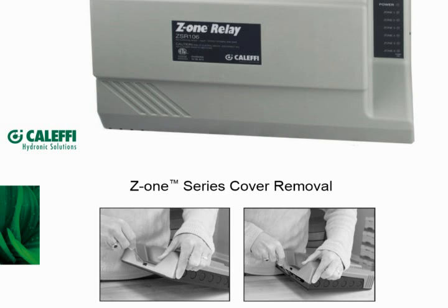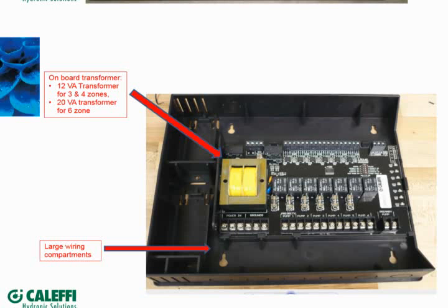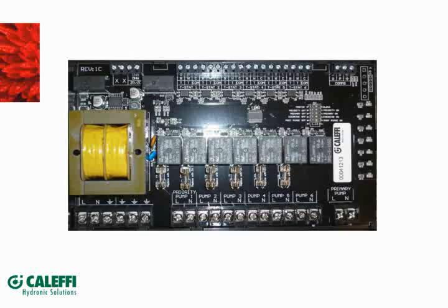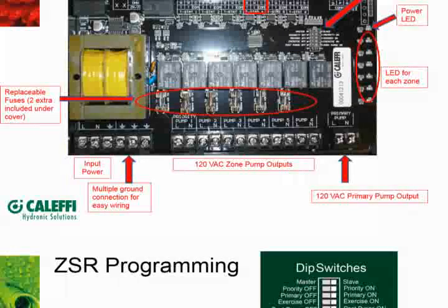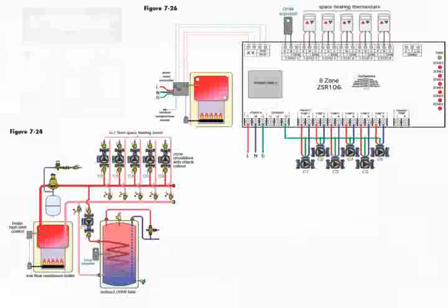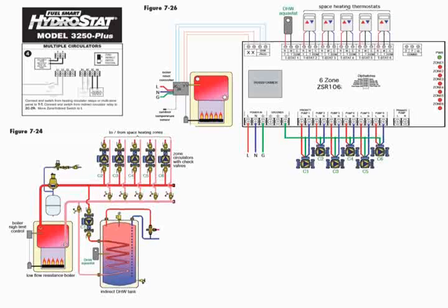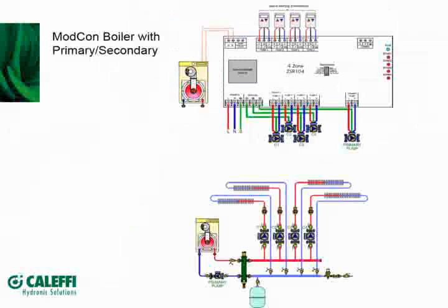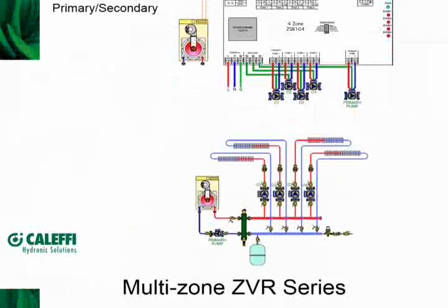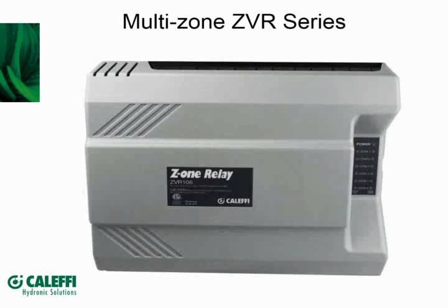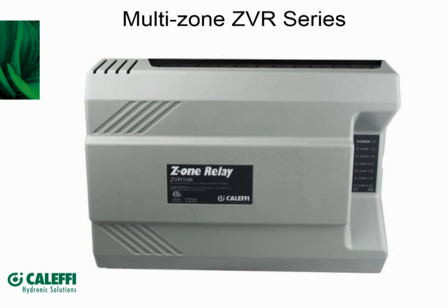Yeah, thanks, Bob. Let me pop through here. Another question while you're popping through, somebody said, have you considered a post-purge on the primary pump? Also, some boilers may require this, to purge out their little heat exchangers after the burner goes off. It's not in there, but you know what, guys? Give us your feedback. Especially software changes, it's not a huge deal to make an upgrade and get it out there. But even on the hardware, we're all ears. We want to keep progressing the product and making it better.